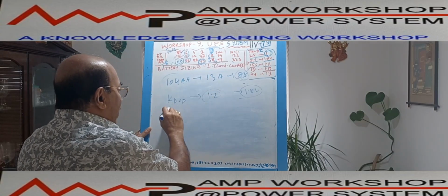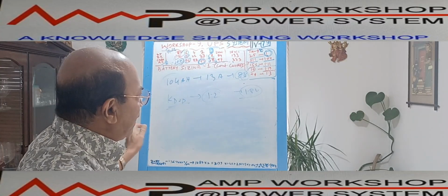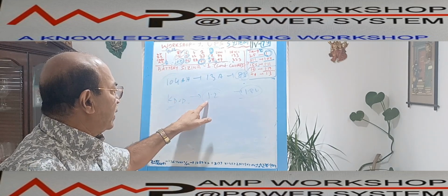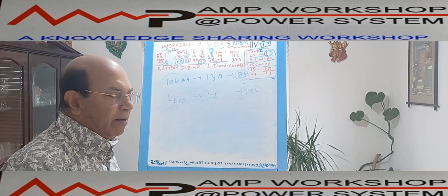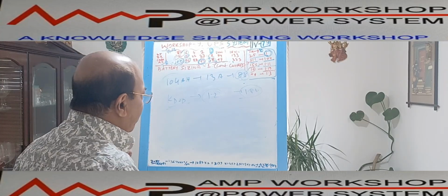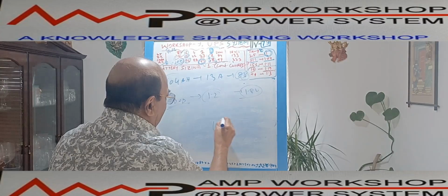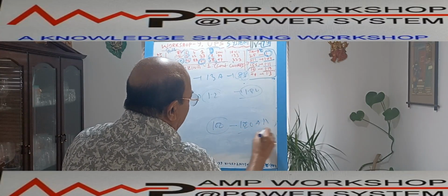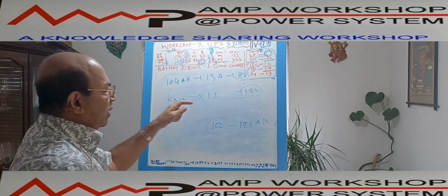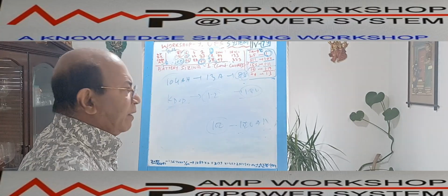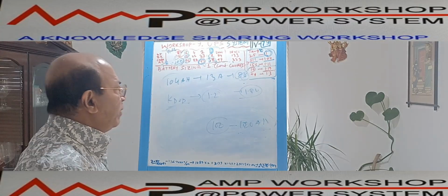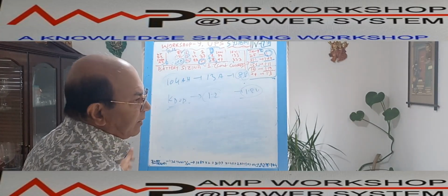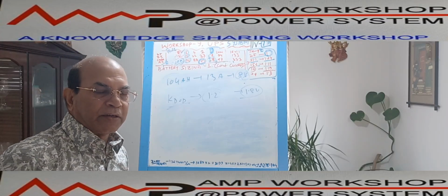That means if I consider KDOD, whatever battery capacity they have declared, over that declared value, I cannot extract the entire value. So if I have a requirement of 100 ampere, I have to consider a battery of 120 ampere hour to cater for this depth of discharge factor. This is another parameter. And the fourth parameter we have to consider is the aging factor. The battery has another factor called aging factor.